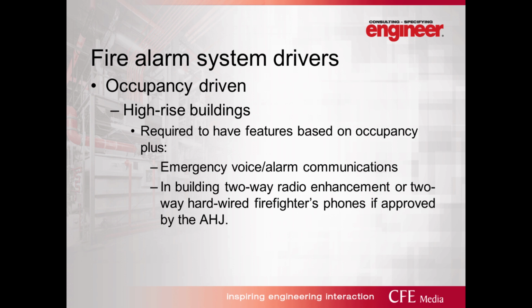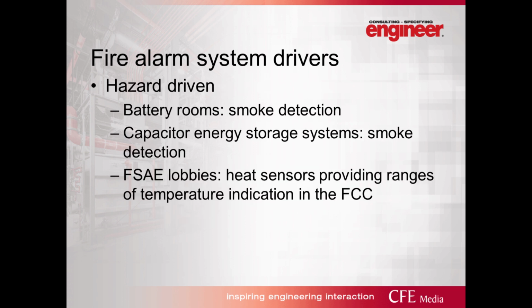And then we have high-rise buildings. High-rise buildings, regardless of occupancy, are required to have emergency voice alarm communications. And high-rise buildings are also getting in-building two-way radio enhancement with two-way hardwired firefighters' phones. Believe it or not, there are still some jurisdictions that require two-way hardwired firefighters' phones and do not recognize two-way radio enhancement. They're few and far between now, but when you're developing these types of designs, it's important to interact with the authority having jurisdiction to verify what their local criteria is as well.